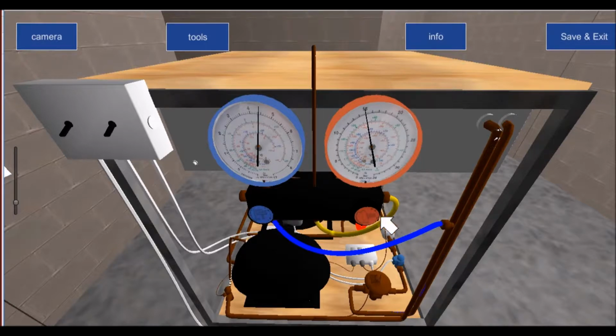The only time we would want to open these two shut-off valves is when we want to either add refrigerant in via the service line, the yellow service line, or when we're taking the gauges off at the end and we want to get rid of whatever liquid is inside the yellow line before we take it off, because we do not want to allow liquid to escape to the atmosphere. So we take every commercially viable step to remove any liquid from the hose lines and make sure that anything that escapes is only a small bit of vapor, down to inadvertent venting. In other words, we have done everything commercially viable to make sure that we haven't deliberately allowed more refrigerant than is necessary to escape.